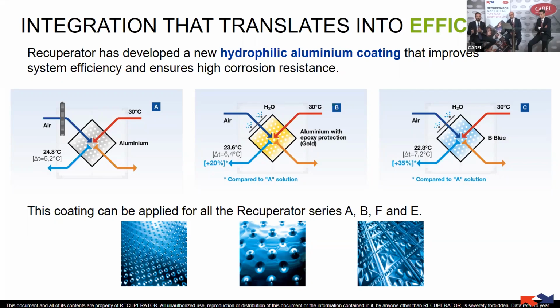The second case instead has a humidification system that replaces the wet pad with the pressurized system that sprays, so it humidifies the air at the inlet and also inside the heat exchanger. So the heat exchanger has to be wetted. But we can do something more. If we replace the standard epoxy protection of the heat exchanger with a special coating, like a hydrophilic absorption coating, we can increase the wettability. So the second key that I mentioned before, the wettability of the plate, enhances the cooling capacity of the whole system.